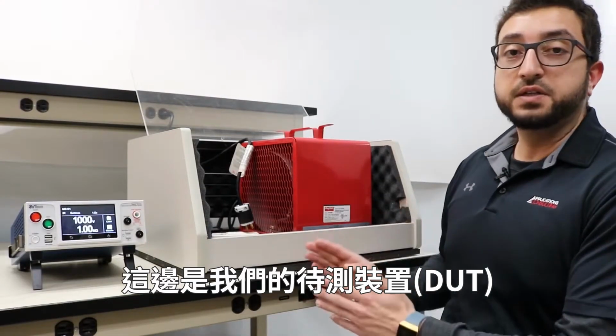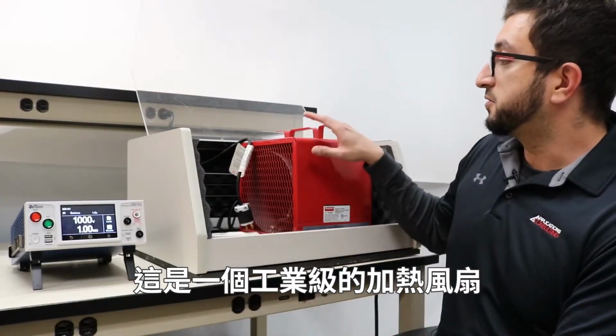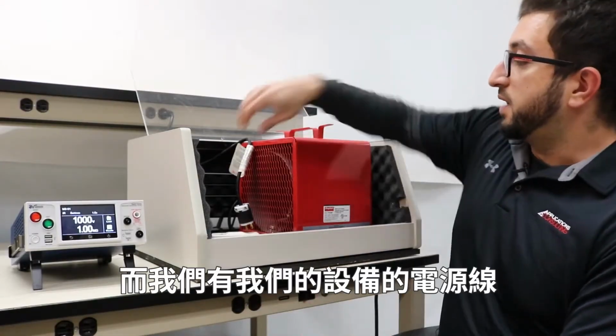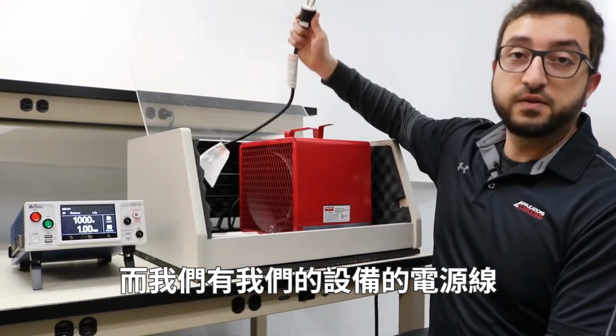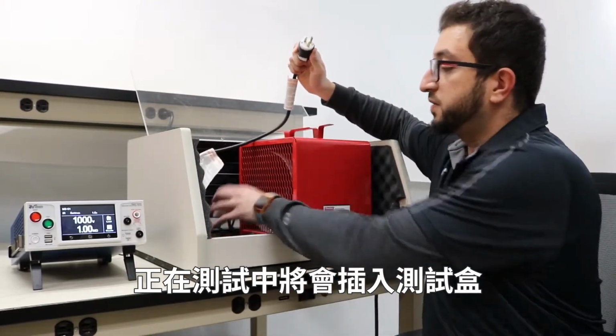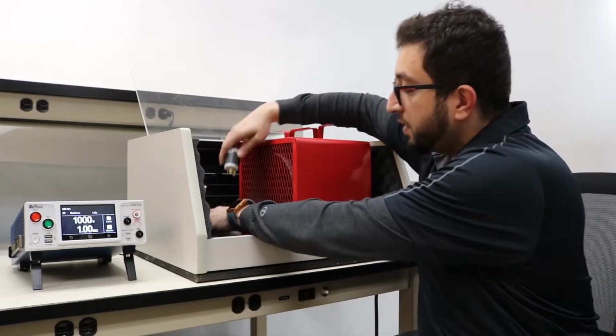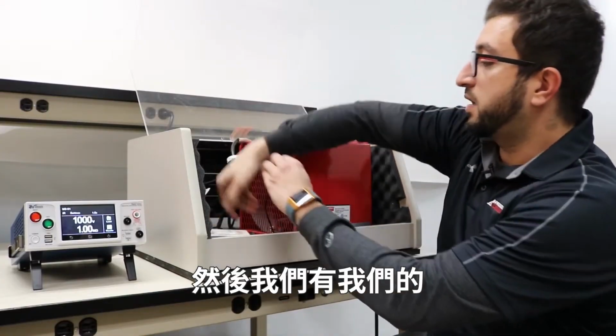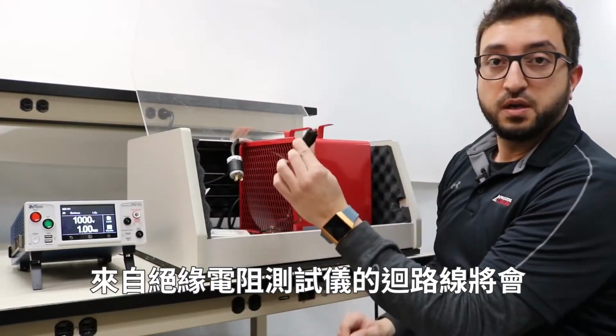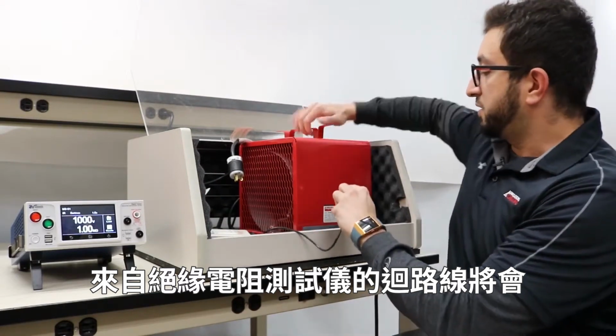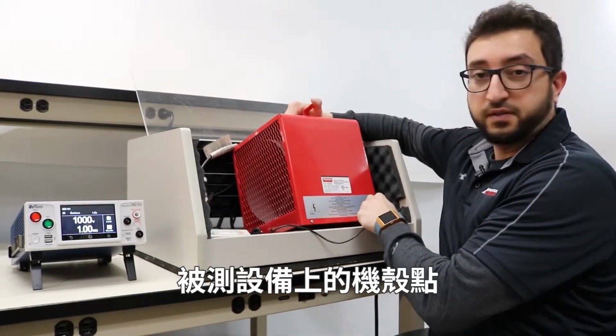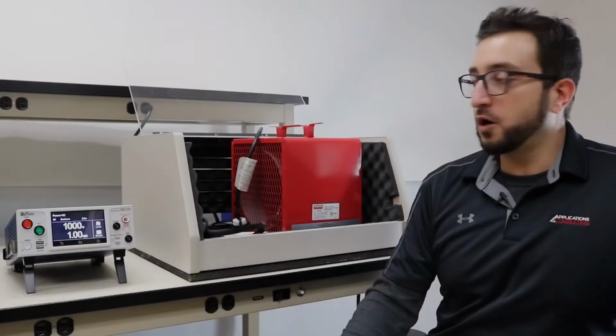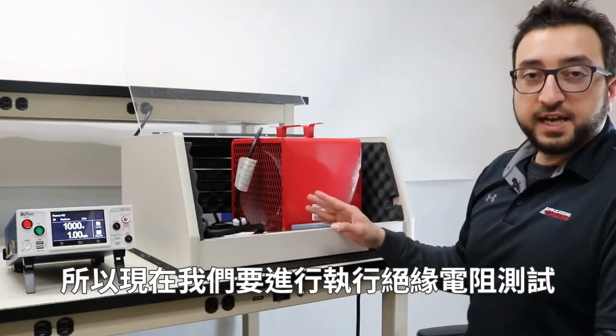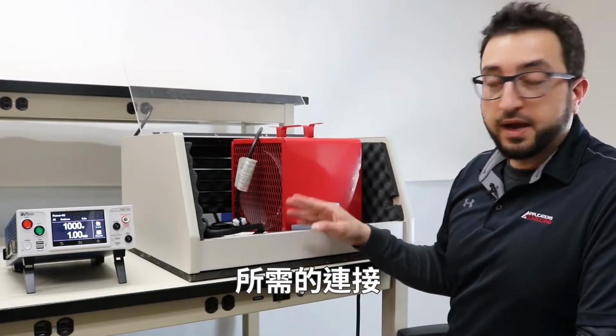On this side, we have our DUT. This is an industrial grade heating fan. And we have the line cord of our device under test that's going to plug into the adapter box. And then we have our return connection from the IR tester that's going to plug onto a chassis point on this device under test. Okay, so now we're going to make the connections necessary to perform the IR test.